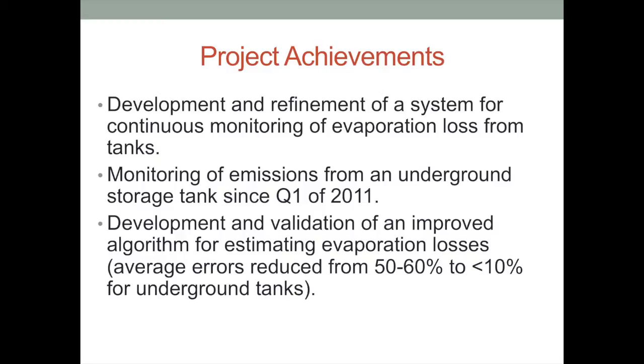The average errors we've seen in the API model have been reduced from 50–60% down to less than 10% for underground storage tanks. If anything, we now tend to overestimate the amount of emissions from underground tanks, whereas the API model was basically predicting half of what we were actually measuring coming off these tanks.